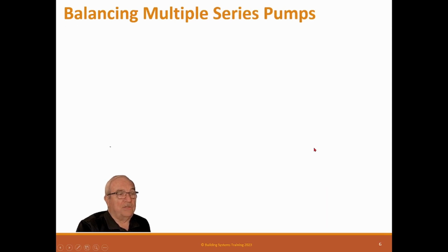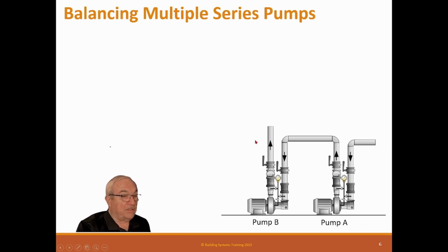All right, what about series pumps? Now, series pumps are a little different and you may not see them very often. They are used mainly in industry and maybe in high-rise applications. And these basically have 2 pumps in series. So the water flows into one and it raises its pressure, then that flows into the other and it raises its pressure, and this is the total pressure going out to the system. These may also be with series chillers. So there may be a single pass-through chiller here and a single pass-through chiller here. It's kind of a unique system. I have seen those before.